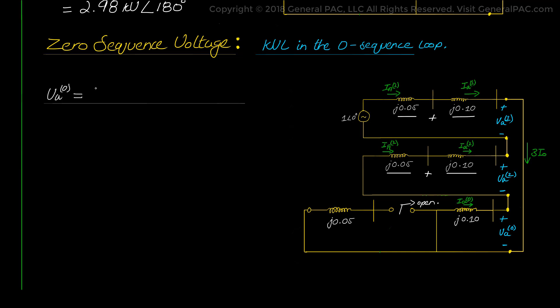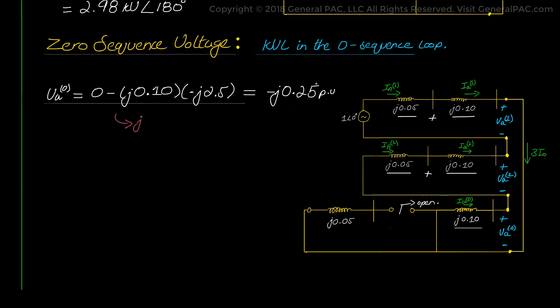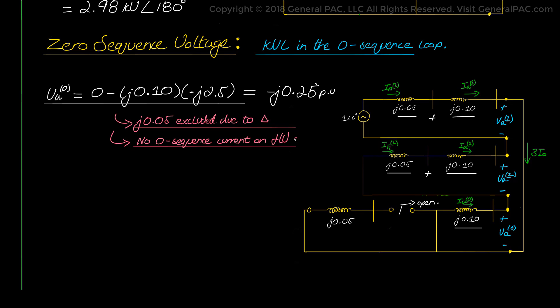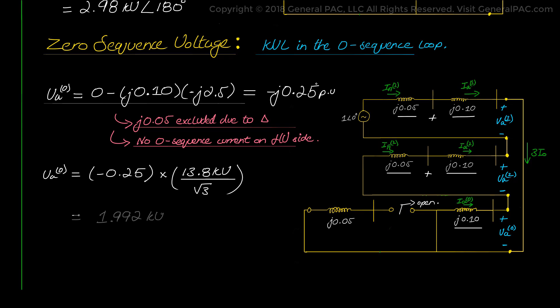For the zero sequence voltage, we apply the same approach: zero sequence voltage equals 0 minus J0.10 times negative J2.5, giving negative 0.25 per unit. Here, the impedance is J0.10 only because the transformer per unit impedance is excluded from the loop due to the open delta — the generator impedance of J0.05 is excluded, and zero sequence current will not flow through the high voltage side. There is also no voltage source for zero sequence. Multiplying by the base gives 1.992 kV at 180 degrees.